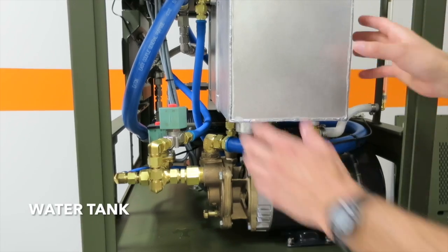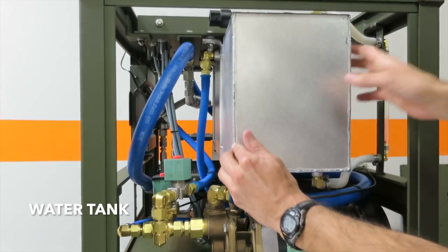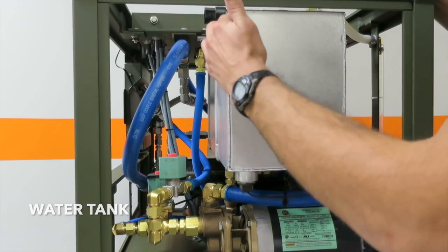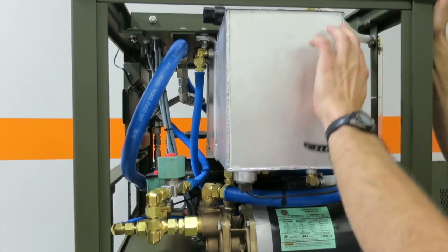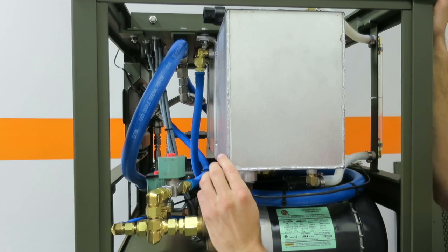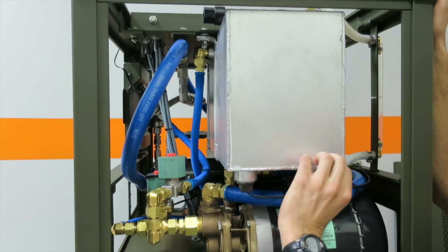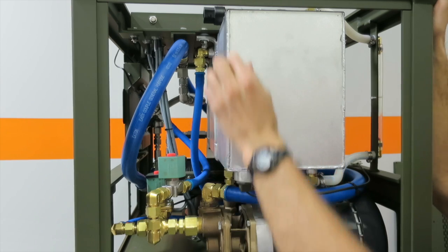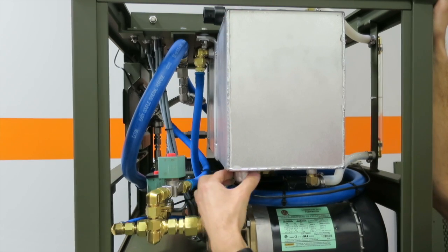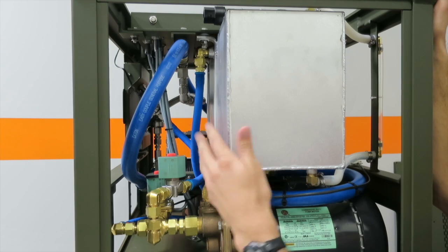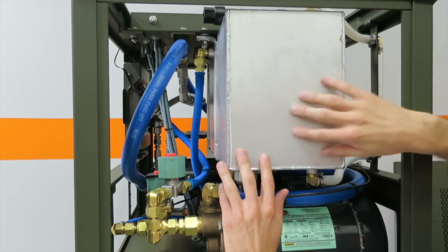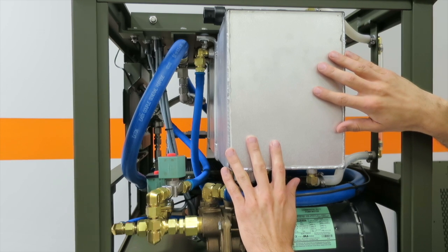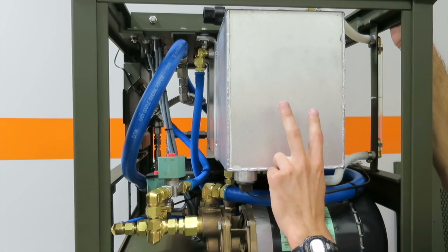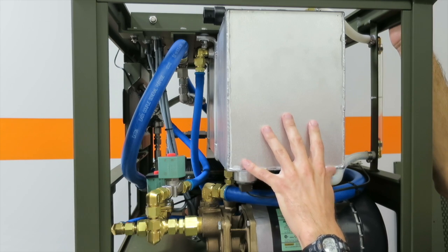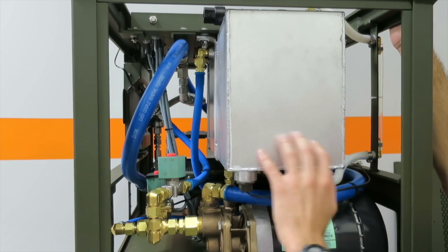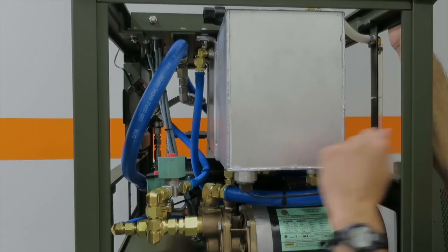Finally, we have the water tank. We actually weld these water tanks in-house and we leak test them. So you should never have any problems with them, but you can check for leaks along the seams, where the couplings are, any of the couplings. These are not meant to hold pressure, so never blow them out with compressed air. There are two vents on top that will prohibit these things from pressurizing or a vacuum forming. But again, never blow these out with compressed air.